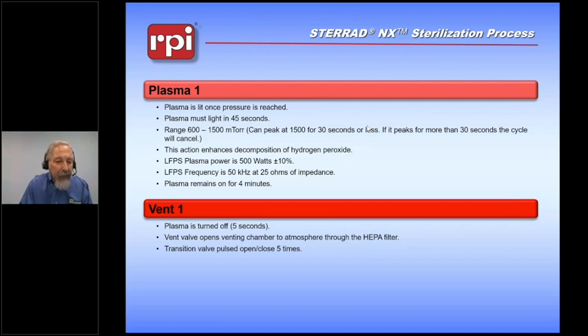The plasma power supply delivers 500 watts, and it will remain on for 4 minutes. Once that 4 minutes is up and we feel fairly confident that we have broken the bonds within the hydrogen peroxide, so that we have released all possible free oxygen and produced all possible water, we will then vent the chamber to air and allow filtered air through a HEPA filter.